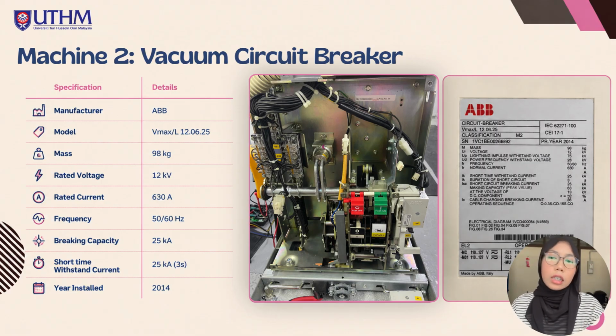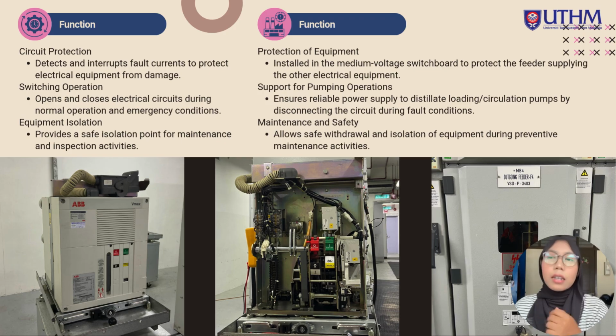The vacuum technology is used because it provides efficient arc extinction and high operational reliability. The vacuum circuit breaker provides protecting, switching and isolation function within the medium voltage network. During normal operation, it allows power to flow through the feeder. During fault condition, it rapidly interrupts the fault current and isolates the affected section.